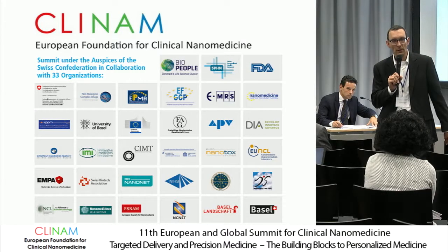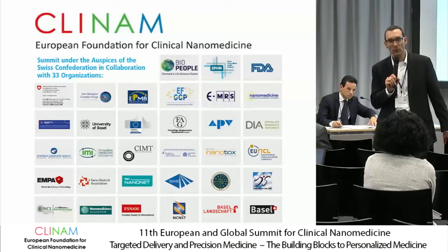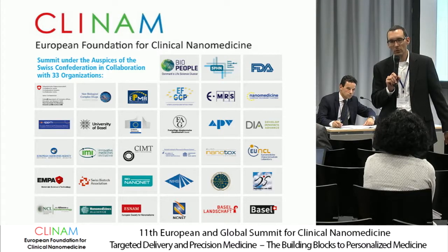Yeah. Coming also to NTA technology a little bit, we do standardization on a GMP level. There are protocols for how to determine standard deviations and errors, for the standards and for the sample. So we offer that, and we do this in close connection with the customer. So basically tailoring the GMP, the IQ, OQ, PQ together with the customer, so they really get the result they want.